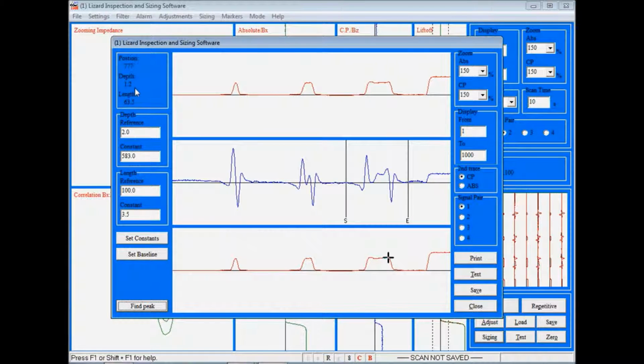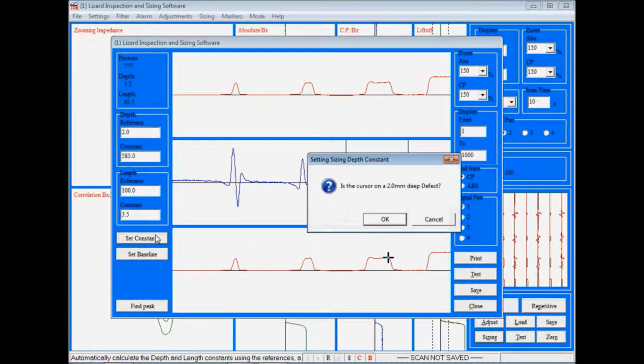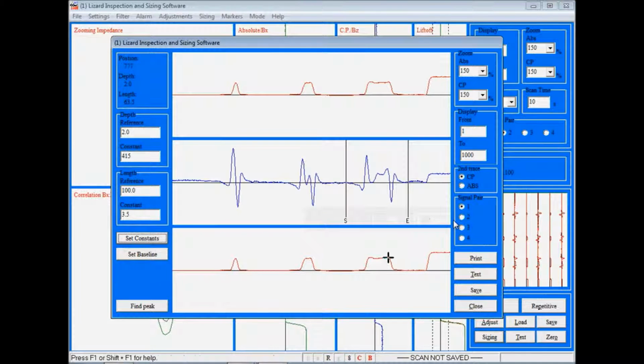You'll see that it's giving me a depth of 1.2mm deep. Now we know that's wrong, so we need to set the constant and tell the system that actually the cursor is on a 2mm deep defect. Click OK. Now it asks me about length. We do not need to know anything about the length to perform this function, so we cancel. Now the system has recalculated and now tells me that the cursor is at a 2mm depth.